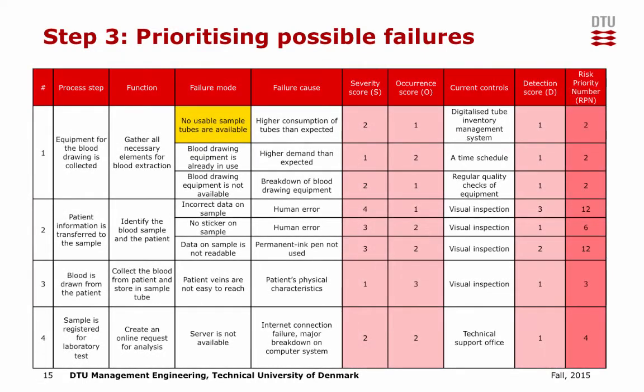The third step is to prioritize possible failures. Each failure mode is given a score for severity, occurrence, and detection, evaluated from the scoring scale mentioned earlier. When finalized, the Risk Priority Number is calculated for each failure mode. The RPN is calculated by multiplying the three scores together. For process step number one — no usable sample tubes available — the scores for severity, occurrence, and detection are 2, 1, and 1, which gives a Risk Priority Number of 2.